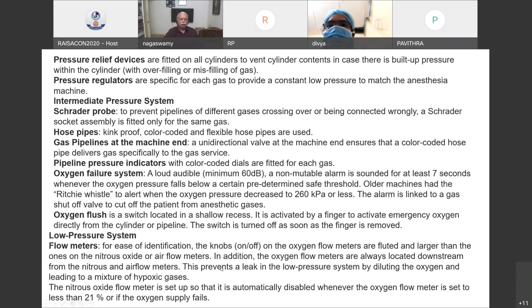So they have a mandatory minimum oxygen flow, which is not available in the older machines. And the flow is variable between 50 to 250. And as soon as you switch on the machine, it will automatically start delivering. So a few machines have this base flow. Once the power switch is on, it will all start working.